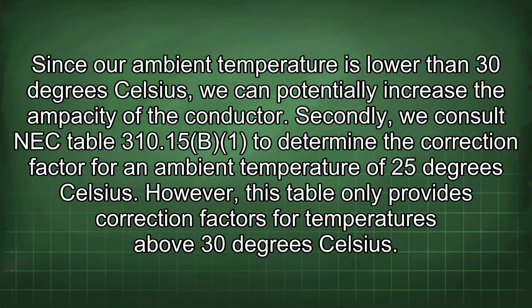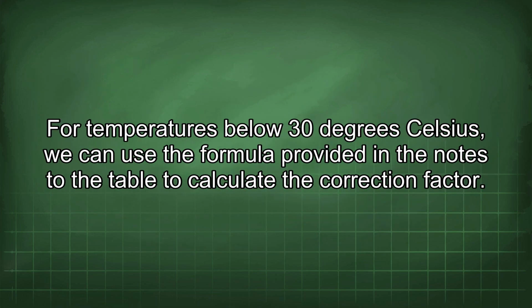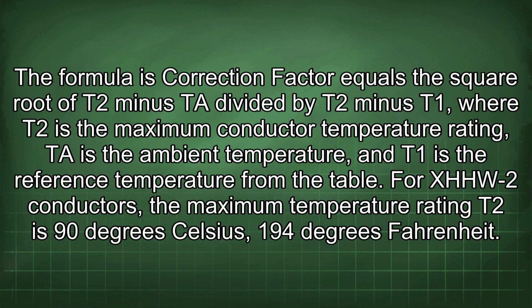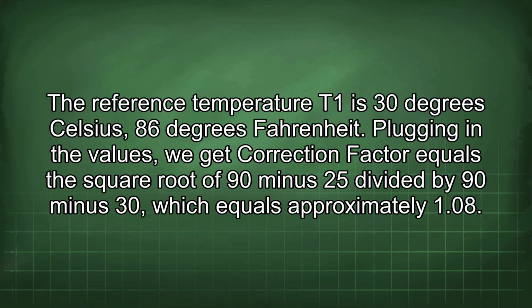Secondly, we consult NEC Table 310.15(B) to determine the correction factor for an ambient temperature of 25 degrees Celsius. However, this table only provides correction factors for temperatures above 30 degrees Celsius. For temperatures below 30 degrees Celsius, we can use the formula provided in the notes to the table to calculate the correction factor. The formula's correction factor equals the square root of (T2 minus Ta) divided by (T2 minus T1), where T2 is the maximum conductor temperature rating, Ta is the ambient temperature, and T1 is the reference temperature from the table. For XHHW-2 conductors, the maximum temperature rating T2 is 90 degrees Celsius, 194 degrees Fahrenheit. The reference temperature T1 is 30 degrees Celsius, 86 degrees Fahrenheit.